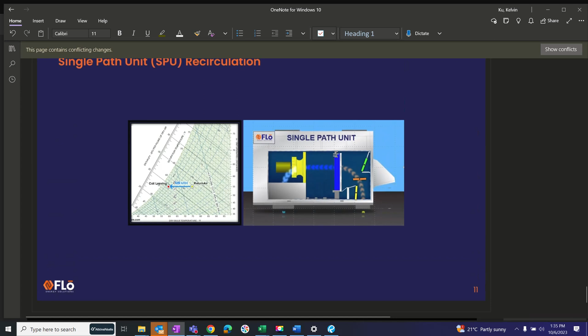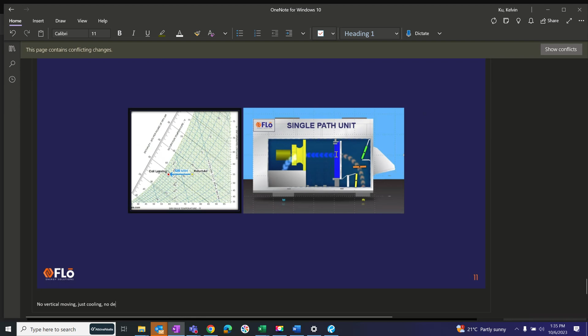This isn't okay for a grocery store, or really any application, on its own, because we also need to bring in outside air. We have 62.1 IAQ requirements for a certain amount of ventilated air, and in your case, for these stores, we have makeup air to provide for some exhaust sources as well. So this unit isn't okay alone.